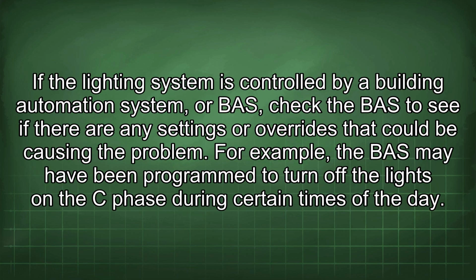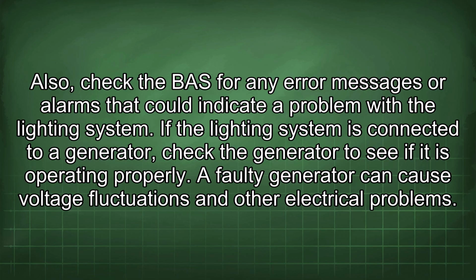If the lighting system is controlled by a building automation system, or BAS, check the BAS to see if there are any settings or overrides that could be causing the problem. For example, the BAS may have been programmed to turn off the lights on the C phase during certain times of the day. Also, check the BAS for any error messages or alarms that could indicate a problem with the lighting system.